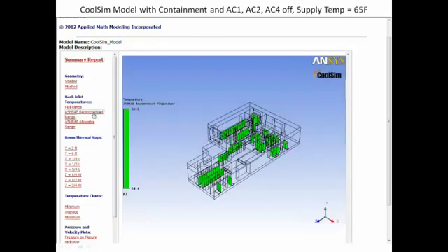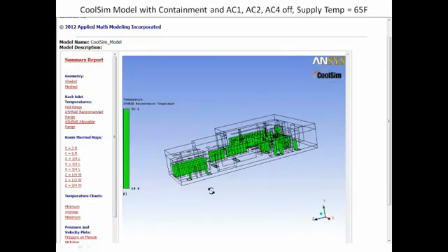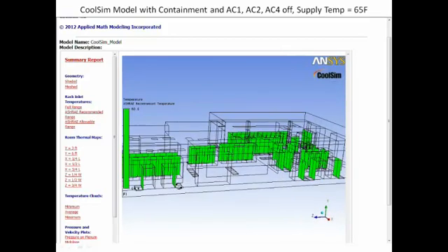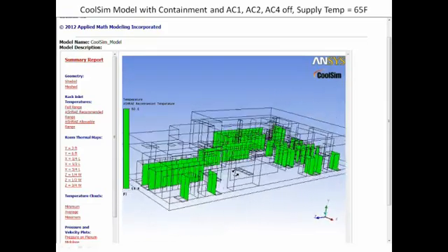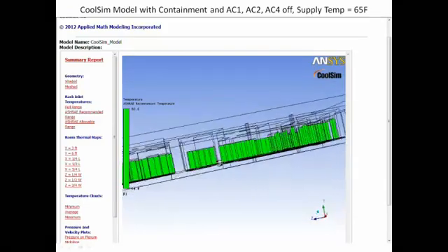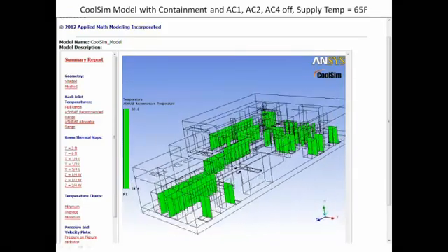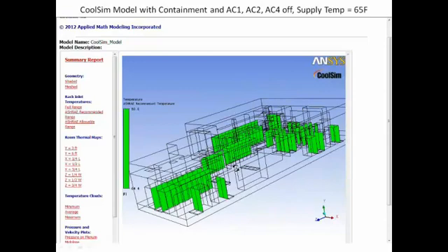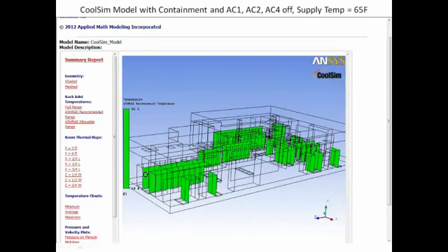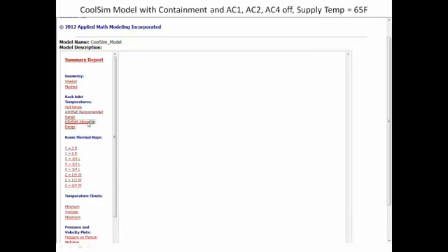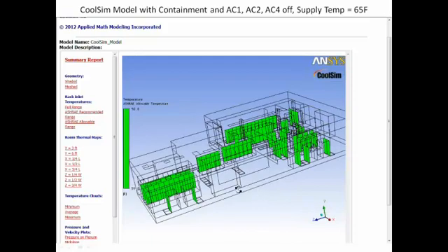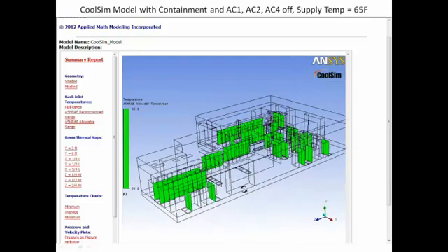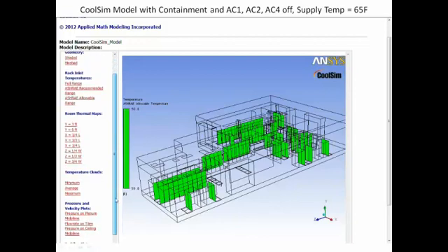So if we take a look at our recommended values, you see now everything's green, which implies we have no racks either over or under. This is, I guess, the Goldilocks test, right? Yeah. The porridge is neither too hot nor too cold. Interesting, if we take a look at allowable here, it is also fine, of course. We've got a broader range to operate in, so everything's fine there too. So that's our optimal case.